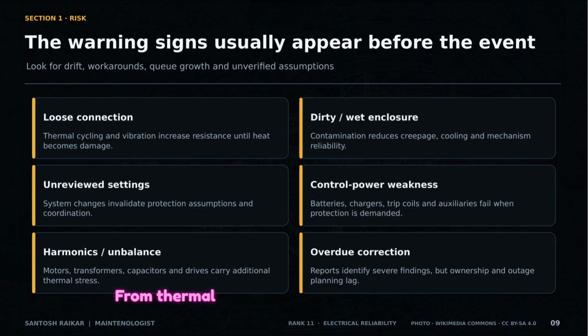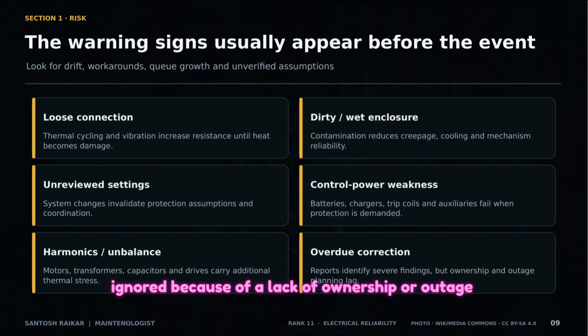From thermal cycling in loose connections to the additional stress caused by harmonics and unbalance. These signals are the precursors to disaster. We also need to watch for management drift, such as when severe findings and reports are ignored because of a lack of ownership or outage planning.